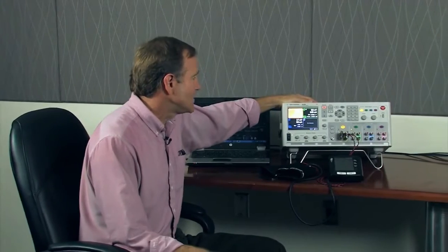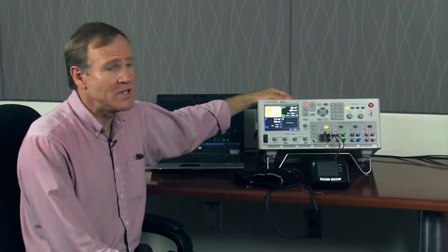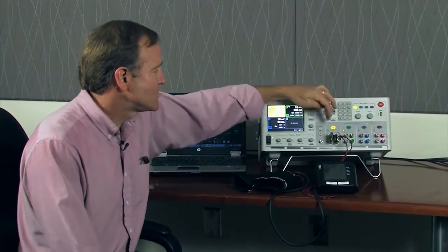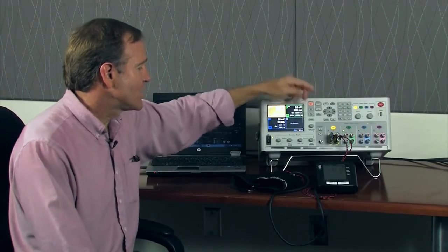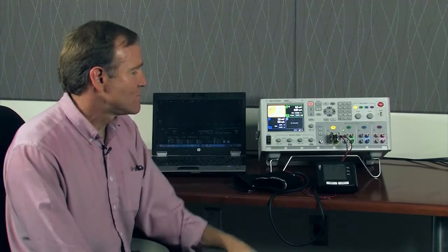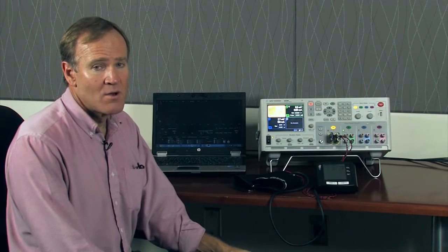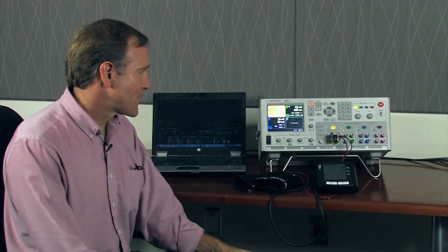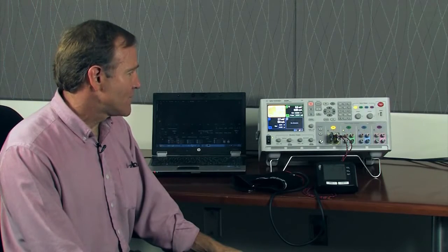This is a DC power analyzer. It's a general purpose R&D tool for an R&D bench. Has 4 modular supplies. We're only using one of those. And we have it connected to a wireless blood pressure monitor. This is actually the world's first Wi-Fi wireless blood pressure monitor. We'll be using this as our medical device for our experiment today.